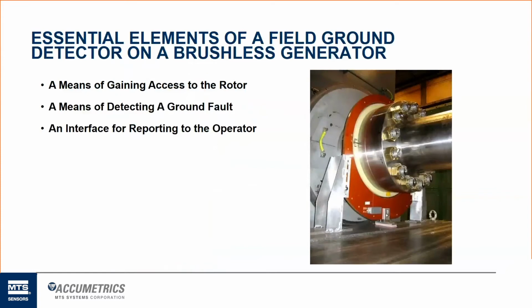So what are the essential elements of a field ground detector on a brushless generator? It's a means of gaining access to the rotor, like I mentioned before. How do you get access to something that's rotating and spinning at 3,600 RPM, on a giant piece of machinery the size of your house? It's a means of detecting a ground fault that may occur within those field windings out on the generator itself. And then it's how you report that information or interface with the customer, with the operator. What type of data are they going to receive?